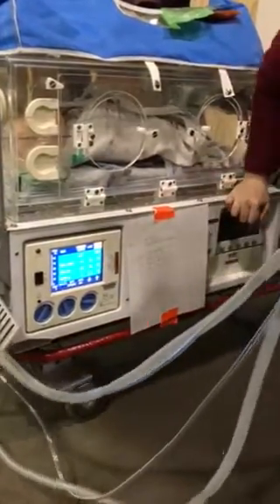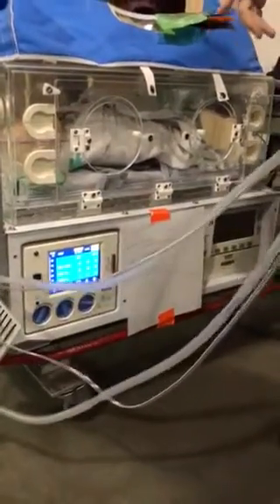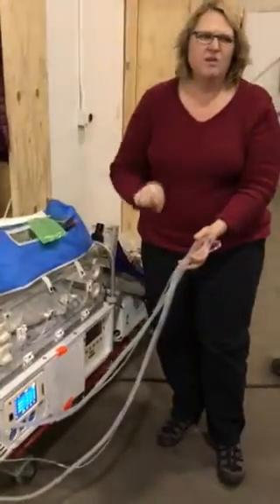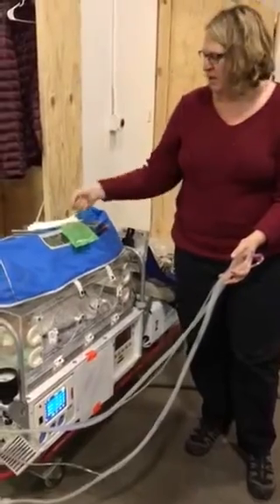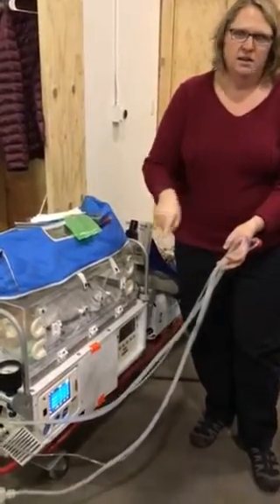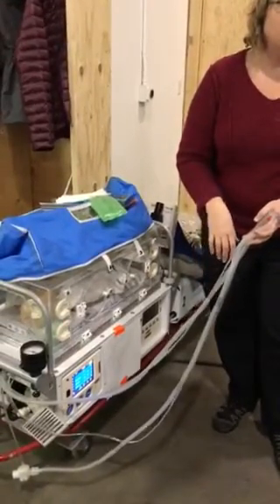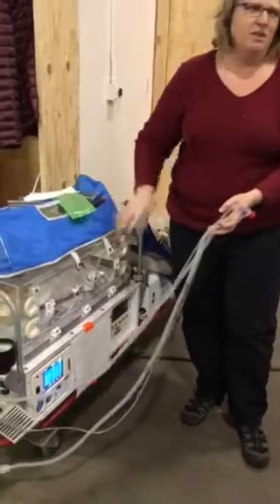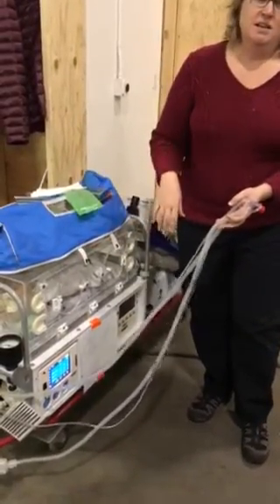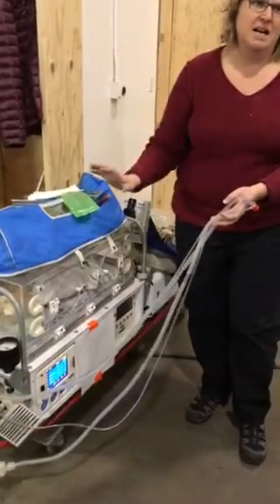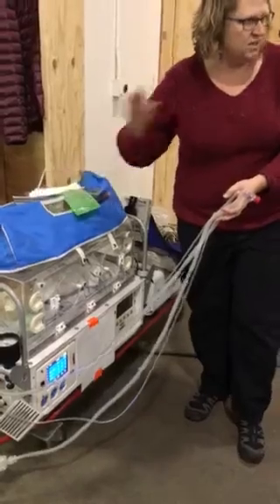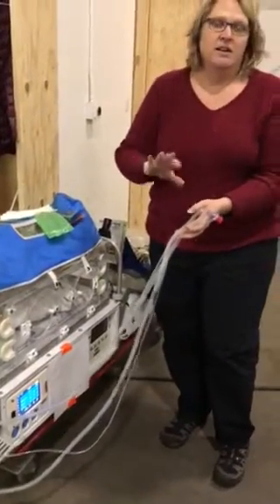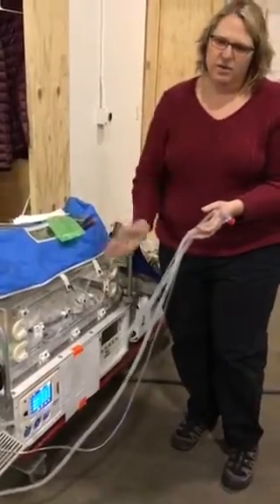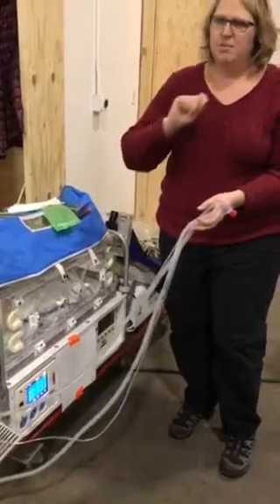That's the thing that I saw a lot of times: people would send it to biomed because it wasn't working, but the PEEP was set higher than the PIP, and the alarms were all out of whack, and they just can't get it to work. Does that make sense? So if you do it very systematically the same every single time, then you don't need a test lung. It took me a long time to find that out, so I'm definitely sharing that information with you. If you just turn it off now and leave the flow the way it is, and I try to reset it again after I turned it back on, for some reason it does not like it. That's where the thought came from that we always needed a test lung. But if you turn everything off and start at 0, do your flow, your PIP, your PEEP, and then your touch screens, and then boom, boom, auto set your alarms.